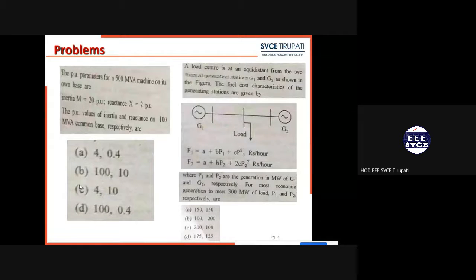Old reactance, old MVA, new reactance, new MVA. As I said, when it's directly proportional, you consider new by old equals new by old. Similarly for inertia, which is inversely proportional, when you keep the ratio as new by old on one side, the rating side you take as old by new. That's the basic mathematics. Once you get the relation, it's very easy to arrange the mathematical formula from it.